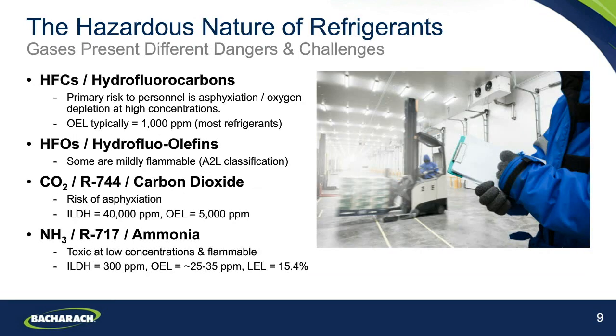Now, if we look at why we are detecting for leaks of refrigerant, it boils down to the simple fact that there can be danger present if a leak is undetected and there is no action taken in the event of a leak occurring. Now, those dangers do vary depending on the particular type of refrigerant being used. Very commonly used, of course, we see HFCs or hydrofluorocarbons, which have been in the market for quite some time now. We're not going to focus here on any of the aspects regarding global warming potential and the environmental impact. We are going to look at safety here. And when we look at HFCs, the primary risk to personnel for most of these gases is asphyxiation or oxygen depletion at high concentrations.